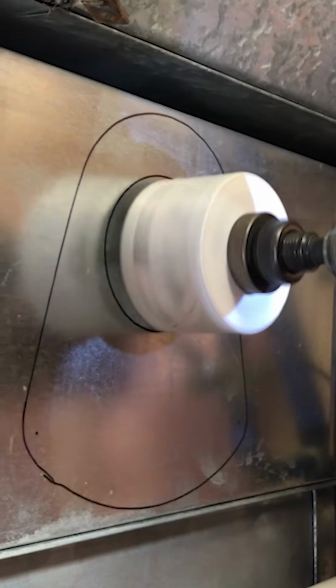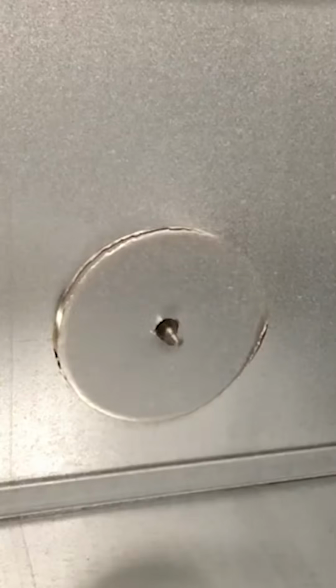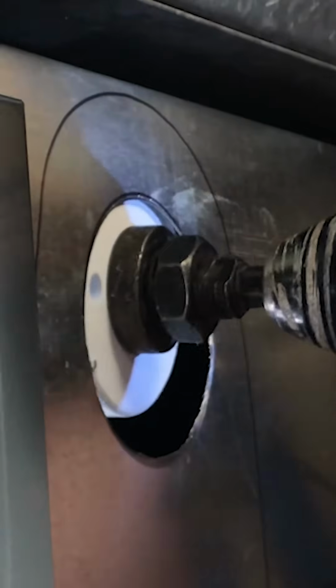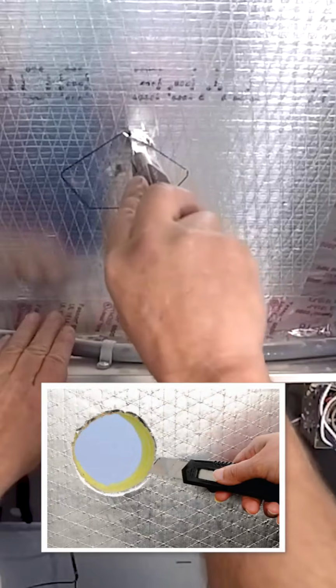If the plenum is sheet metal, you'll need to use the appropriate metal cutting tool to get the job done. I used a drill with a 3 1/4 inch hole saw. If you're putting the access hole above the evaporator coil, when you drill the hole into the ductwork, be careful not to drop the metal piece from the hole you're drilling. If your plenum is insulated ductboard, a razor knife should get the job done.